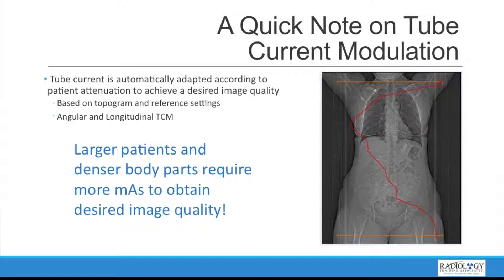The main point of tube current modulation is that larger patients and denser body parts are going to require more mAs to obtain the same desired image quality. So if we have more attenuation in the beam — more attenuation seen on the topogram — then the mAs will have to go up.